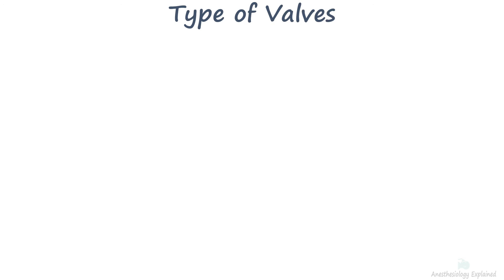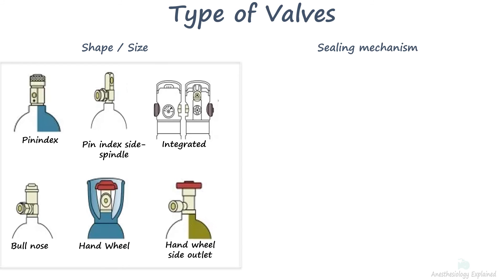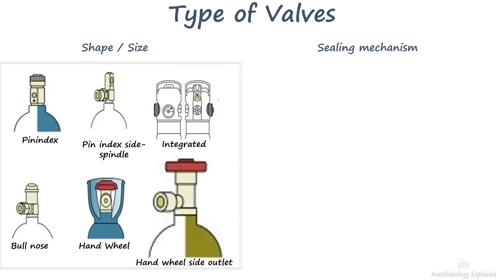Cylinder valves are classified based on shape, size, and the sealing mechanism used. Depending on the size of the cylinder body, different shapes and sizes of valves are used. Smaller cylinders have pin index valves, while larger cylinders have bull-nosed valves. Some valves have a side spindle and wheel which closes and opens the valve outlet, but broadly they fall under pin index or bull-nosed type.